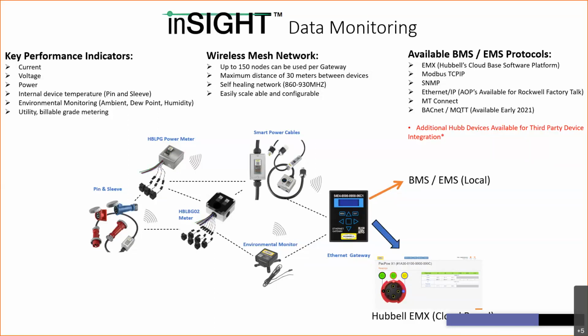The types of data fed out from the gateway from all these devices are key performance indicators: current, voltage, power, and internal device temperature, which is strictly in the pin and sleeve. That's a patent we have here at Hubbell, embedding the technology directly into the pin and sleeve, so you get the temperature directly at the connection point.